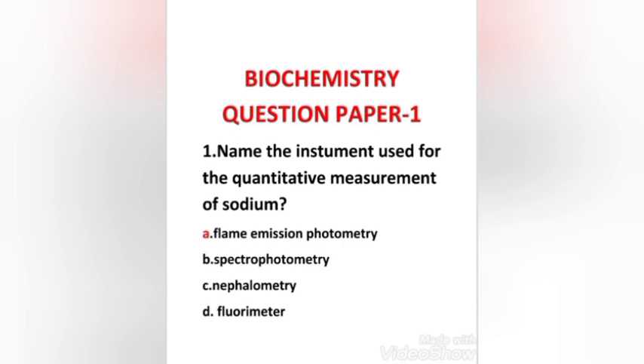The principle of flame photometer is based on the measurement of the emitted light intensity when a metal is introduced into the flame. The wavelength of the color gives information about the element, and the color of the flame gives information about the amount of the element present in the sample. It is used in clinical laboratories for determining sodium, potassium, lithium, and calcium ions in body fluid.